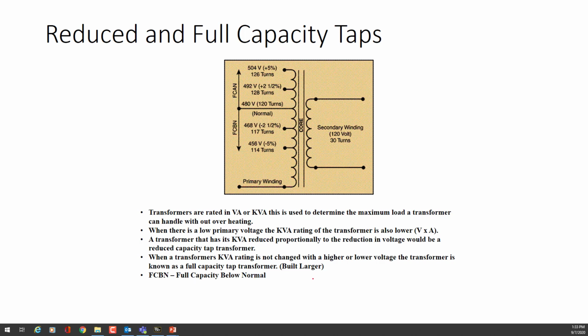Okay, so that means I could have a low voltage, drop it down to that minus 2.5 or minus 5%, and everything's fine. I can still load it up to whatever the kVA stamped on the nameplate is. So that means it's engineered a little bit better or a little bigger. FCAN, full capacity above normal, same thing. I can go to a higher voltage tap and I'm fine. I can still load it up to whatever the kVA rating is. And then we have RCBN, reduced capacity below normal, and that's where we would have to watch how much we load that transformer up to. Whatever the nameplate stamp is, I would have to subtract off the 2.5% or the 5% of that. So multiply that 2.5% by the kVA rating and then subtract that from the actual kVA rating, and that'd be the new maximum load I could put on that transformer, or its maximum rating, I should say. Okay, so a little bit on that.